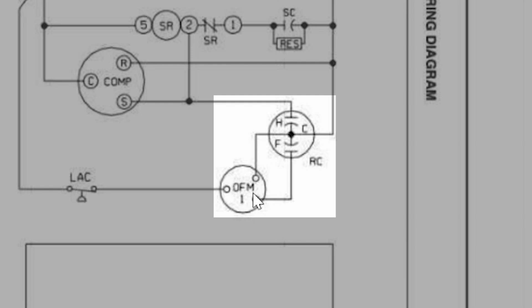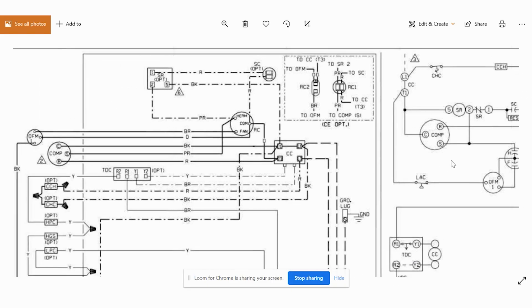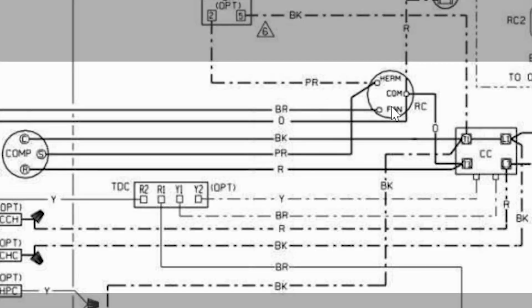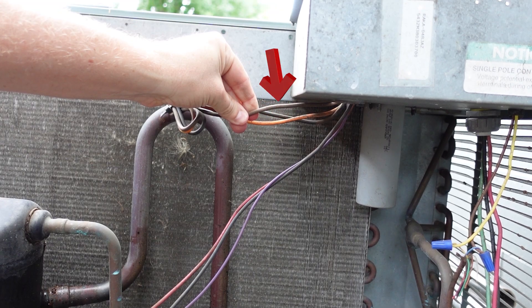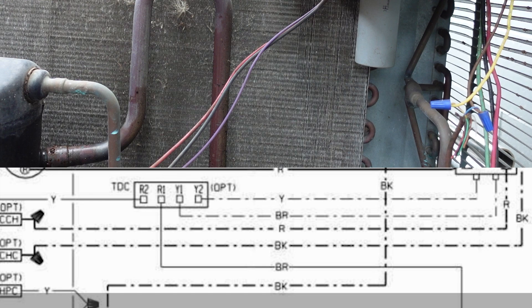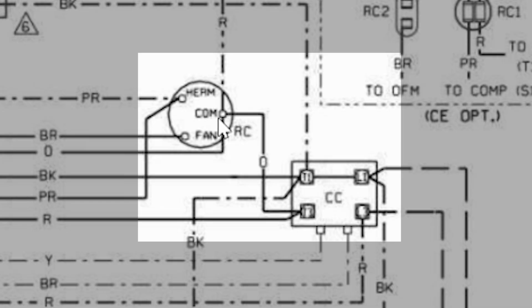One is going to go to the run side of our outdoor fan motor. Now here, it doesn't even list any terminal names, but if we go over to our fan motor over here, outdoor fan motor, we can see that fan is a brown wire. And that is actually, it doesn't say that here, but that is our start winding on our fan because it's the one connected to the fan terminal on our capacitor.